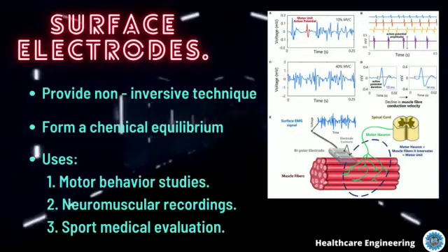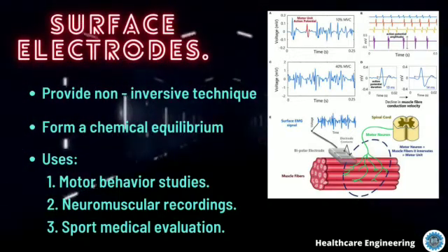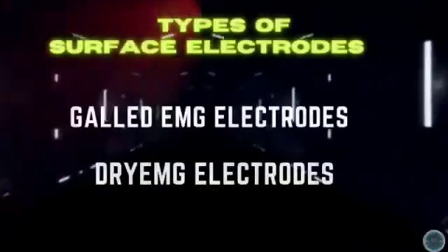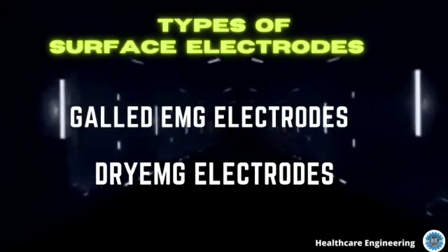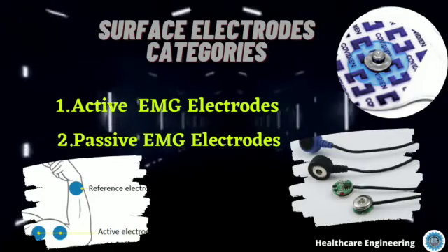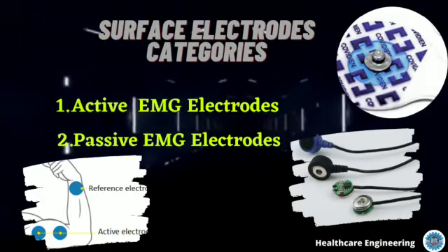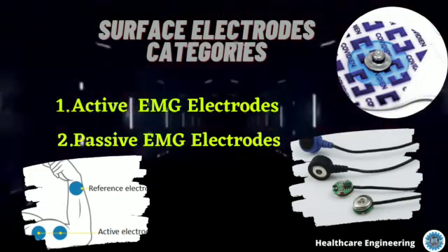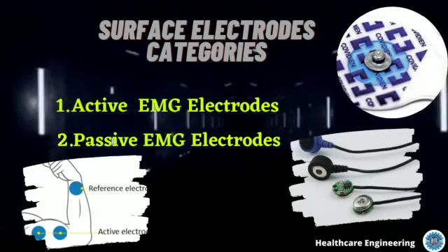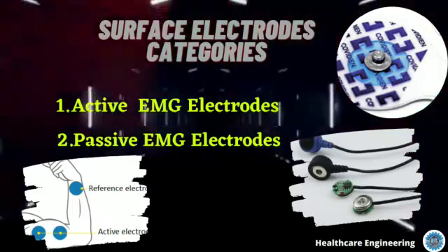Surface electrodes are used in motor behavior studies, neuromuscular recordings, and sport medical evaluation. The types of surface electrodes include gelled EMG electrodes and dry EMG electrodes. They can be further divided into active EMG electrodes, which contain a pre-amplifier attachment, and passive EMG electrodes, which are connected to an external amplification circuitry.